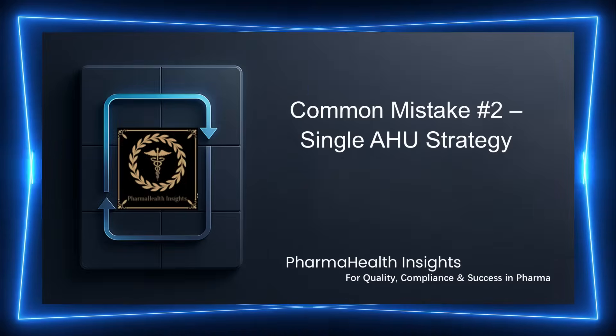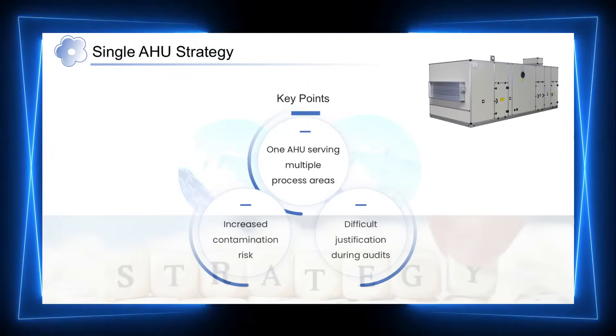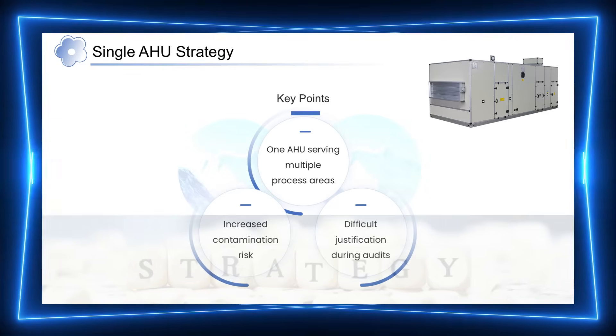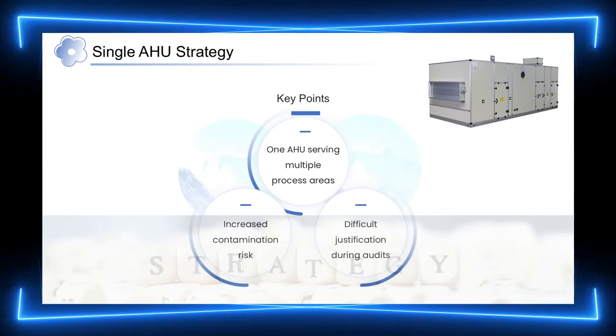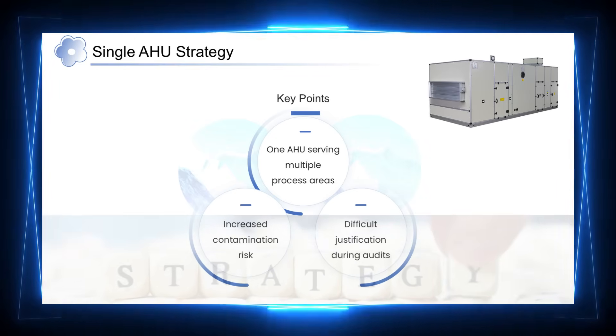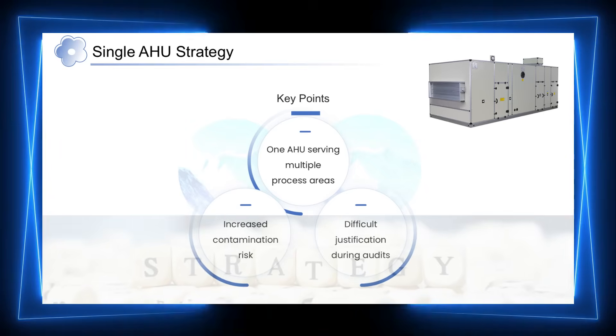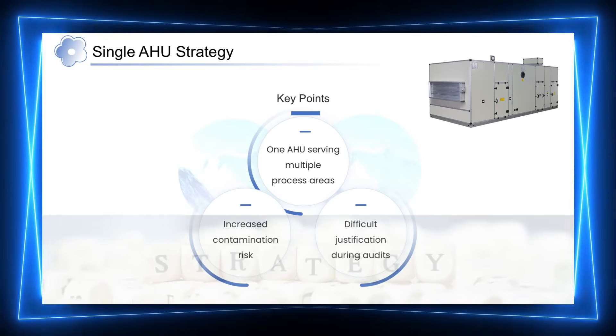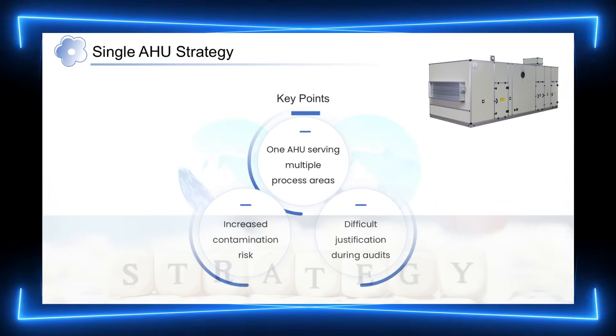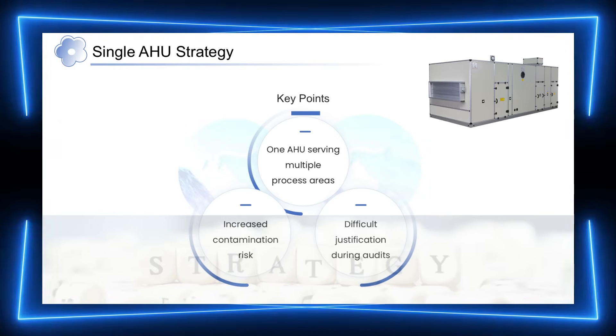The next mistake often arises from cost optimization. In many facilities, a single AHU is used to serve multiple manufacturing or support areas as a cost-saving or space-saving measure. While this may appear efficient from an engineering perspective, it creates challenges from a GMP standpoint. When different processes with different risk profiles are handled by one AHU, the potential for cross-contamination increases. During audits, justifying such a configuration becomes difficult, especially when clear segregation and risk control cannot be demonstrated.